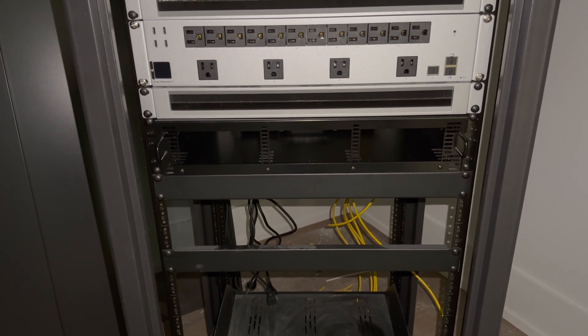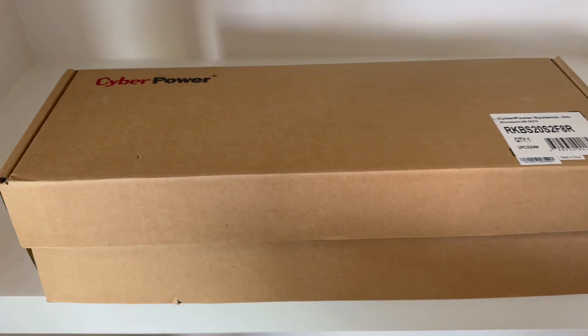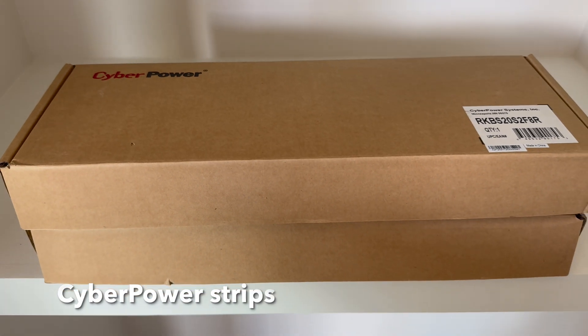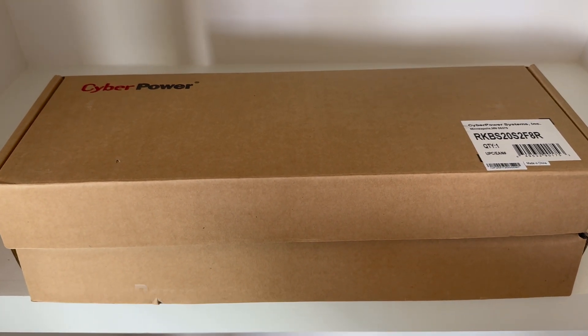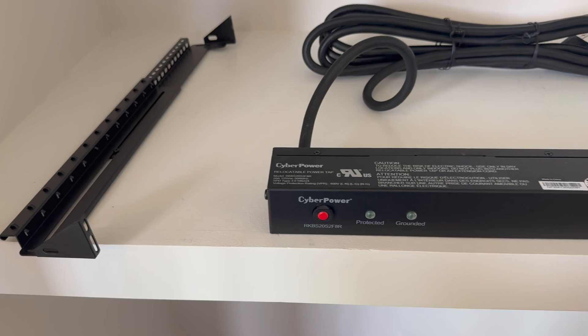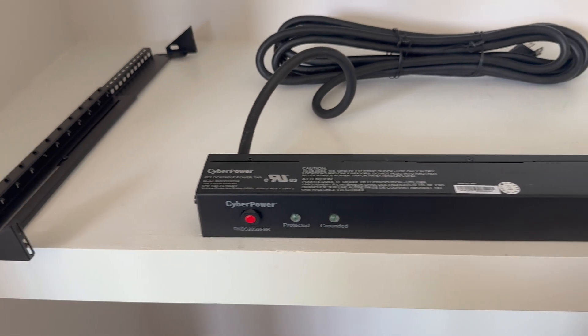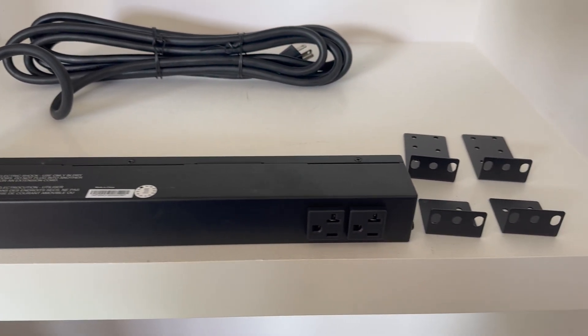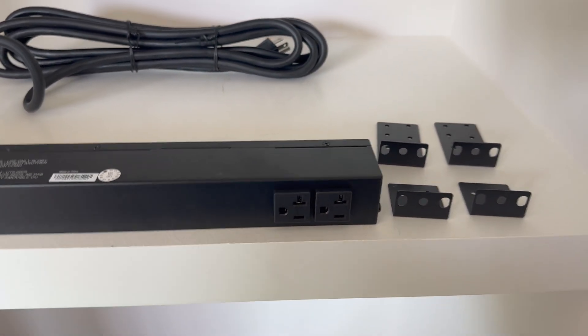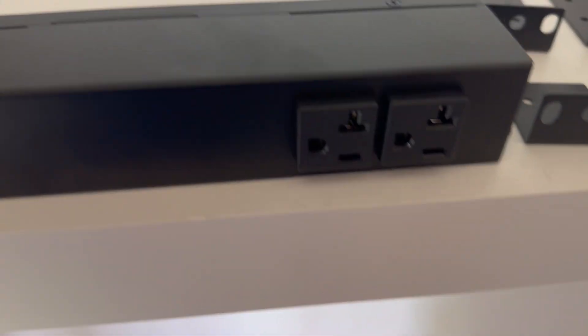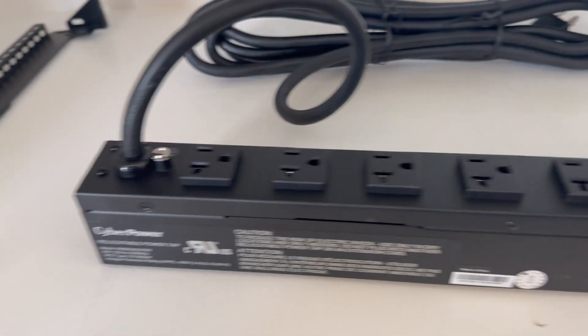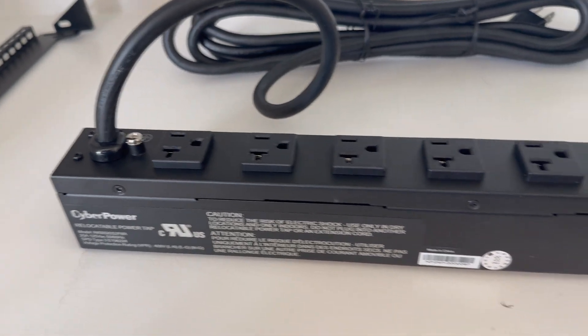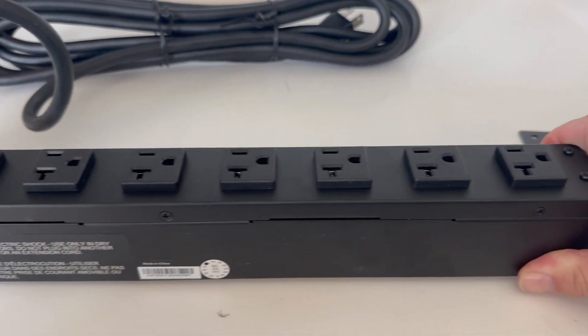Last but not least, I'm going to add two power strips to the back of the rack. We have three separate 20-amp circuits in the AV closet, and I'm going to use two of them to power this rack through power strips. So the PDU Pro will be plugged into one power strip, and at a later point I'll get the redundant power supply and plug it into the other power strip. That way, all that's coming out of the rack are two 20-amp power cables.